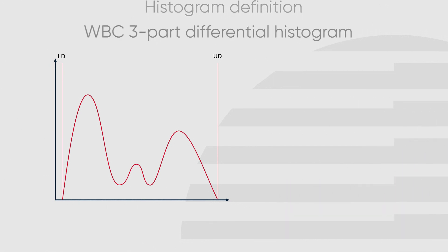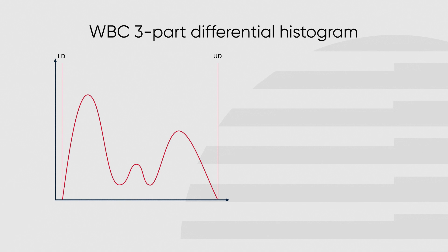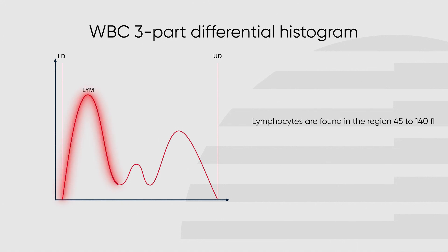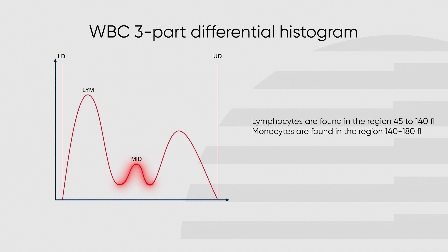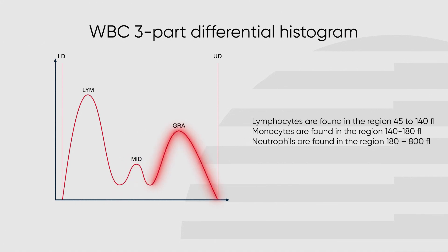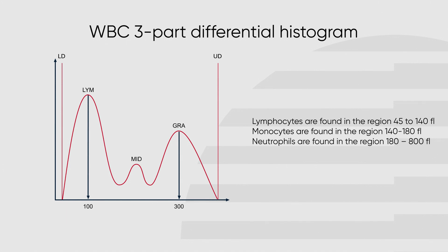In a three-part hematology system, white blood cells are further separated into three populations: lymphocytes, mid cells (mainly containing monocytes), and granulocytes (mainly neutrophils). Lymphocytes and granulocytes are visualized in two distinguishable peaks centered at about 100 femtoliters and 300 femtoliters. Mid cells are situated in between these two main population peaks.